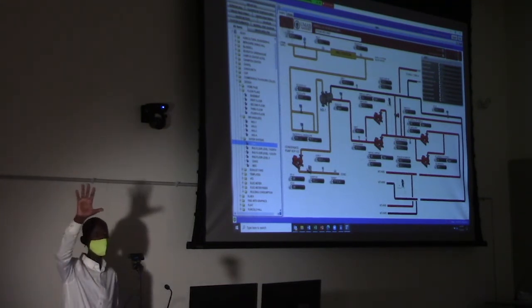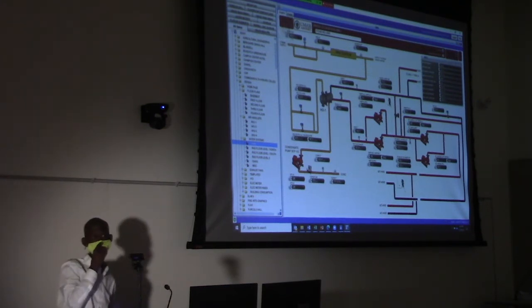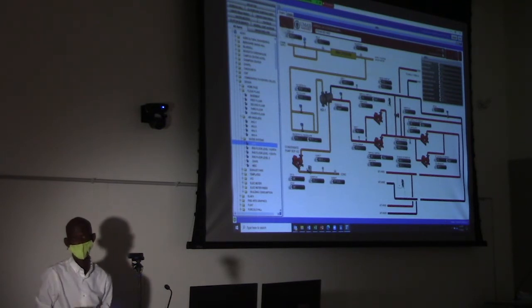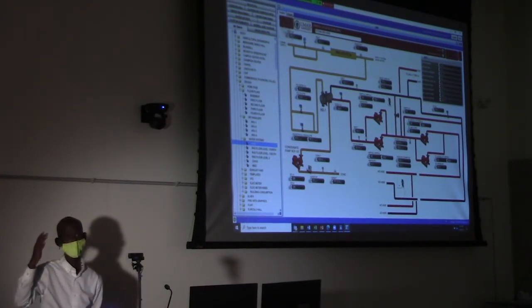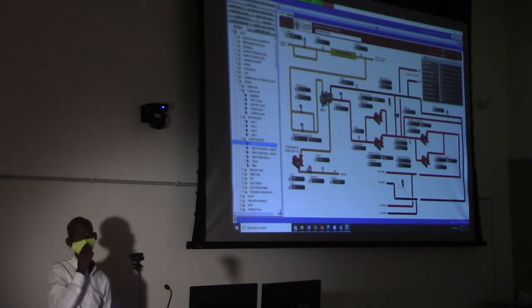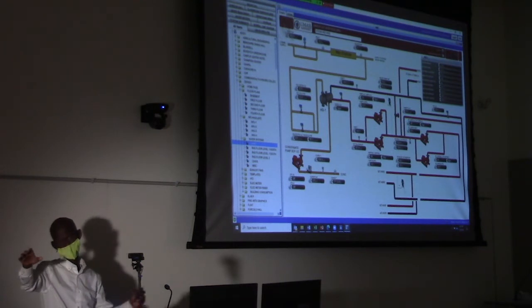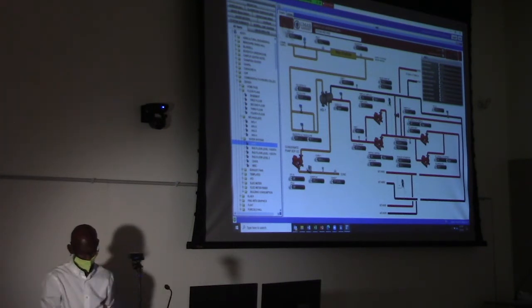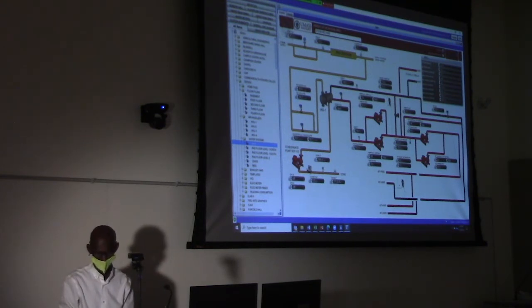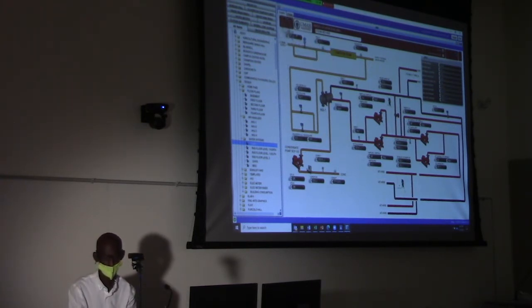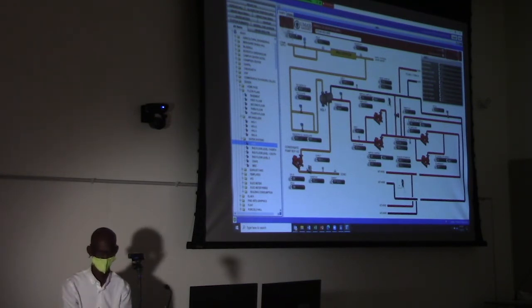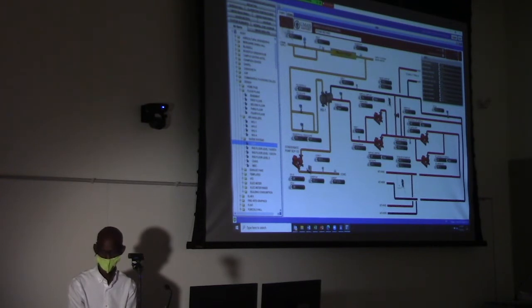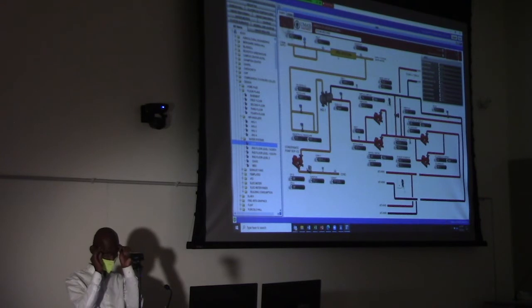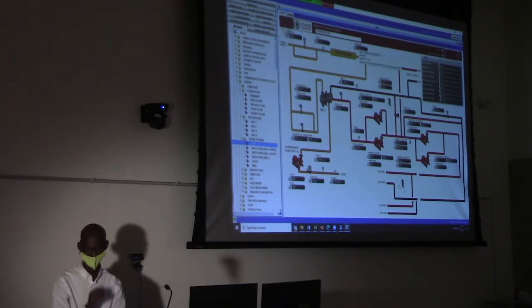We have steam coming from the power plant. Usually the power plant sends it either as high pressure or medium pressure. High pressure is over 200 or 400, but this is medium pressure, which is 90 psi. 90 psi is a lot, so it gets reduced to 15 psi so that it can go to some buildings. Steam flow coming into the building right now is 475, and it enters at 16 psi, but it's reduced by the pressure reducing valve to 9.7 psi.